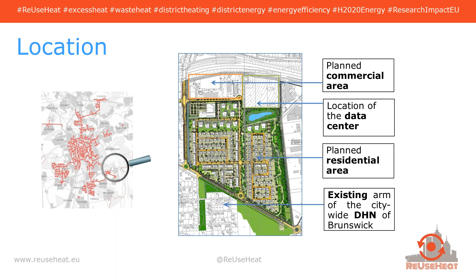This simple sketch illustrates the main idea of the project. We have a residential area with 400, potentially up to 600, housing units, and a data center with many megawatts of thermal energy as excess heat. The data center operator transfers its excess heat to the cooling water cycle, which is forwarded outside the data center where it's used to supply the heat pump. The warm side of the heat pump feeds the low temperature district heating network.